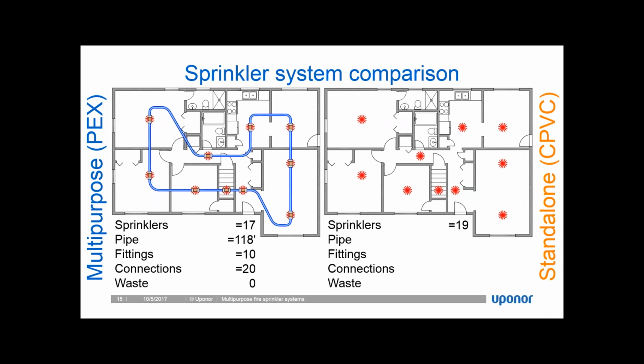For the most part, when we design and send a material list out to a contractor, we don't include any elbows for that installation, because the installation can be done without adding additional fittings to get around corners. So basically we go from sprinkler to sprinkler. The piping comes in large coils. So for this project, let's say we use a 300-foot coil. When I'm installing the pipe between sprinklers, I will take the coil and I will measure out how much pipe I need on either side of, or to connect the 2 sprinklers together, and that's it. Whatever pipe I don't use, it goes back in the coil, or I use for the next sprinkler. So there's no waste produced when I'm piping a system using large coils like that.